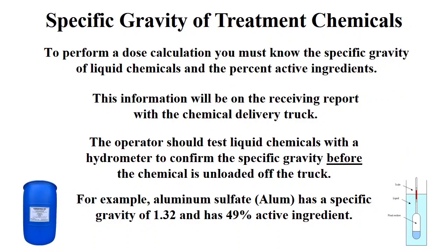To perform a dose calculation, you must know the specific gravity of the liquid chemical and the percent active ingredient. In each chemical delivery, the truck driver should give the plant operator a receiving report with this information. The operator should test the chemical on every delivery with a hydrometer to confirm the specific gravity before the chemical is unloaded off the truck.